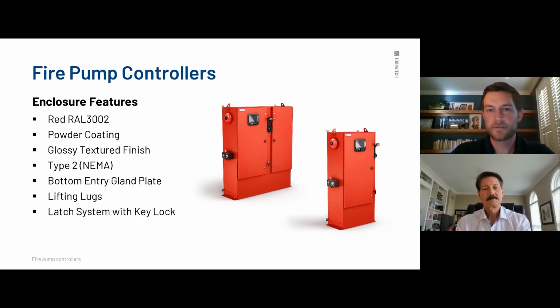Okay, that's everything for the alternate power. This is just going to be some enclosure features. We've got the specific coating, the red paint that you see there. It's a powder coating, glossy texture. Standard is a NEMA 2 enclosure. We can go NEMA 3, NEMA 4, NEMA 4X, and other NEMA types as well. But standard from the factory is going to be NEMA 2. In all of our control panels, this is the one with the automatic transfer switch. This is the one without it, obviously.